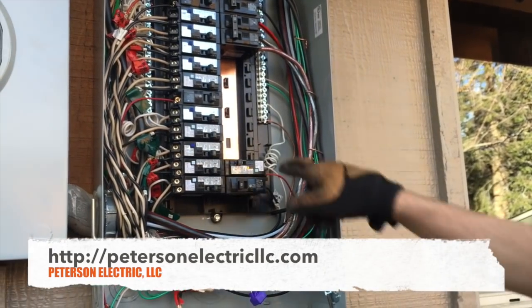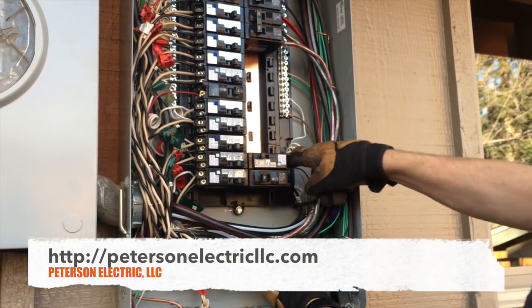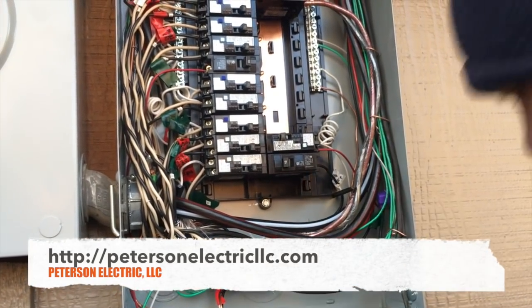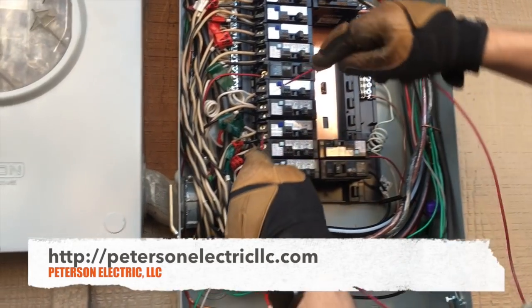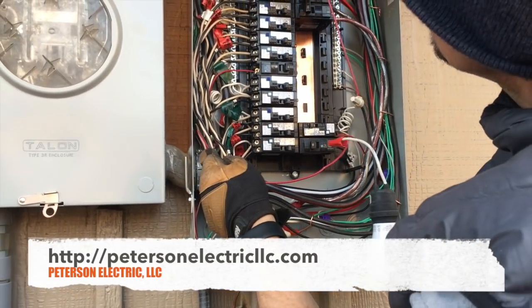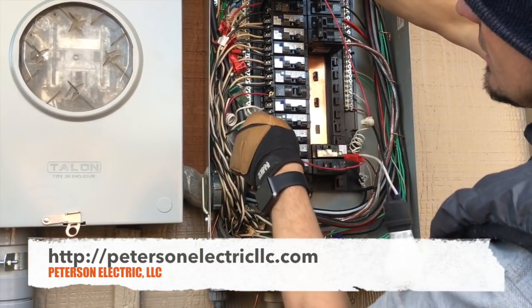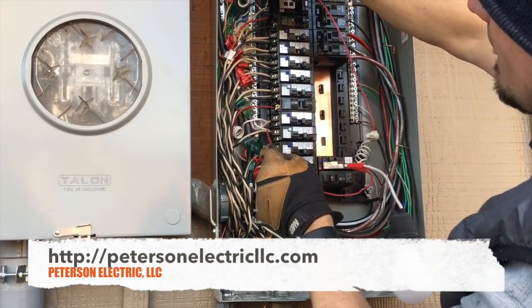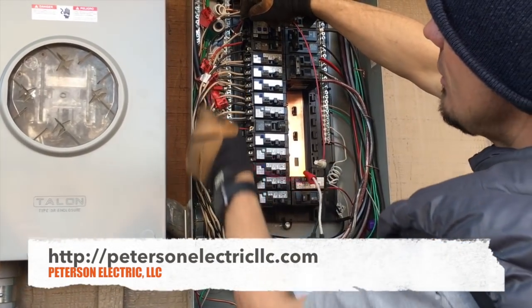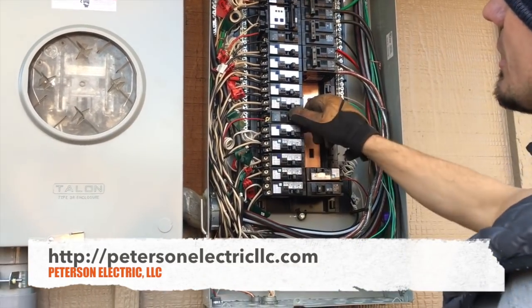When I went to turn it on, I noticed I had the grounded conductor — the white neutral — on the top side. What's supposed to happen is once you've turned the breaker 180 degrees it goes to the bottom. Here's how I test my arc faults: I come in and check that the light bulb is on, and so on. As soon as I hook up to a different potential I can trip my dual-function AFCI, and I actually prefer to do that because I don't really trust the test buttons. I want to fault it to make it seem like there's a real fault, using an alternate path of current after the light bulb. A normal breaker will never do that — it'll just stay on.